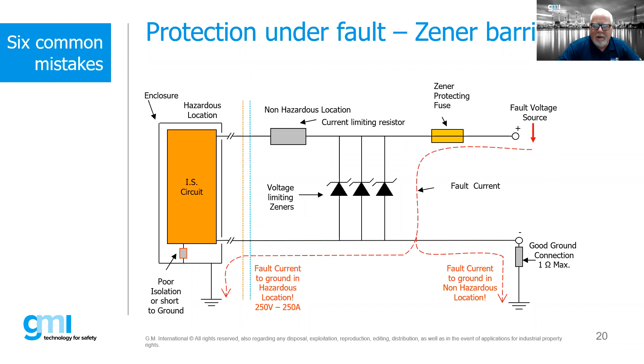As you might imagine, one of the mistakes we do find with regards to the selection, design and installation of IS is our clean earth. That's a big issue, which we'll talk about here in just a second. So our common mistakes, as I mentioned, no dedicated intrinsically safe earth. Again, Zener barriers, in order to work, require that dedicated earth.